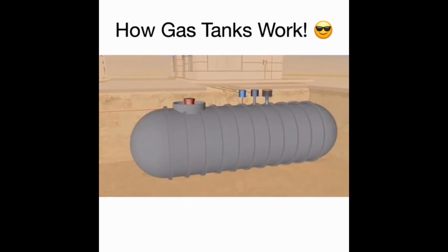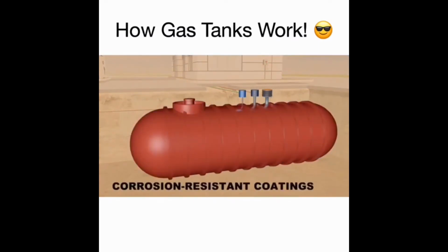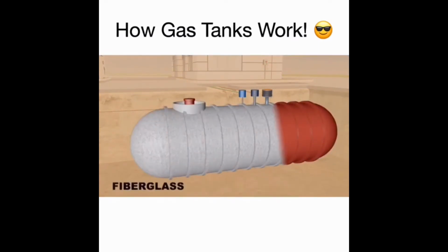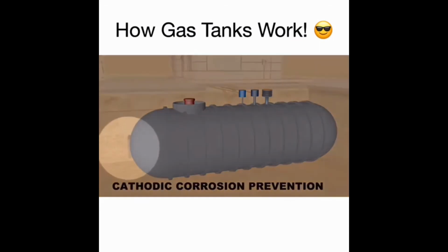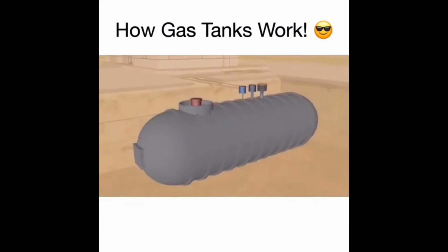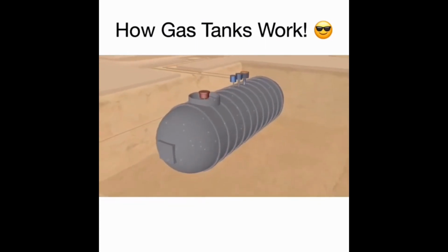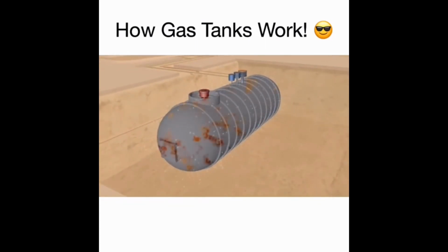Thanks to a nationwide upgrade campaign, the vast majority of underground storage tanks and pipes feature corrosion-resistant coatings, or they're made entirely of resistant materials, like fiberglass. When uncoated steel tanks are used, cathodic corrosion prevention systems are required. Corrosion, or rust, is caused when moisture in the soil draws off electrons from iron molecules in the steel. Applying a slight electrical current, basically a stream of free electrons, helps keep the iron molecules intact.